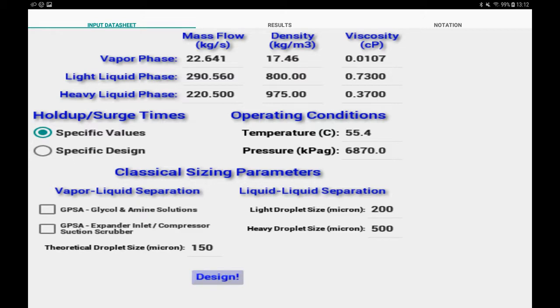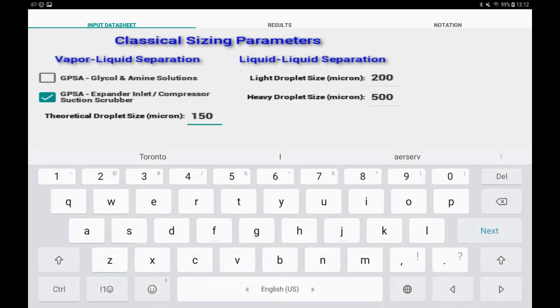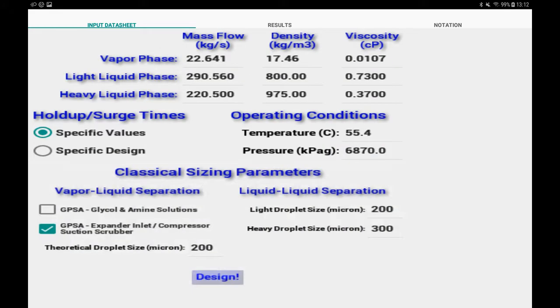We had another option which will be discussed later. Classical sizing parameters can also be adjusted to improve the accuracy of classical methods. The vapor-liquid calculations for theoretical method, and the liquid-liquid calculations for all classical methods, are highly affected by the assumed liquid droplet sizes. You can change the default values based on your own engineering judgment or empirical data of your design case.